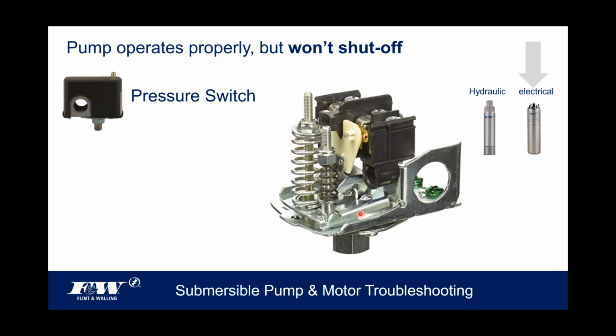Well, that's what this switch is supposed to do. It's supposed to shut the pump off. Now, in order for it to shut the pump off, the pump has to build the pressure. But there are times that the pump builds plenty of pressure and it still won't shut off. The reason behind that is these contacts right here. I've got a highlighter hovering over that area. There's a set of contacts or points on both sides of this pressure switch that make and break as the pump is powered on and powered off.